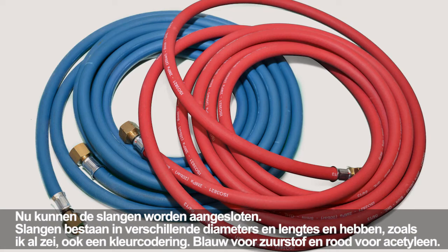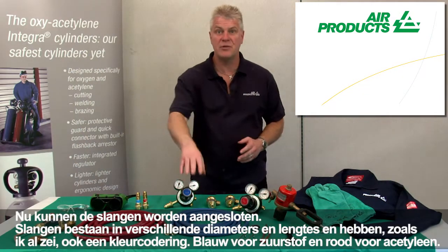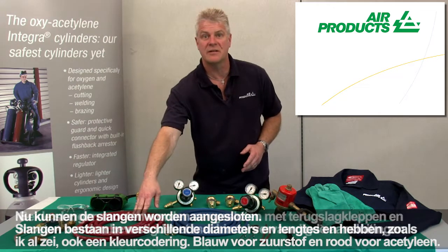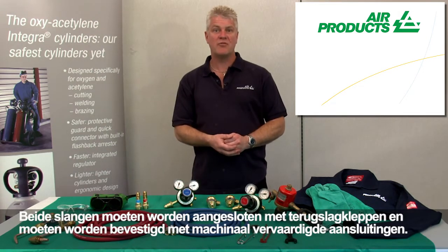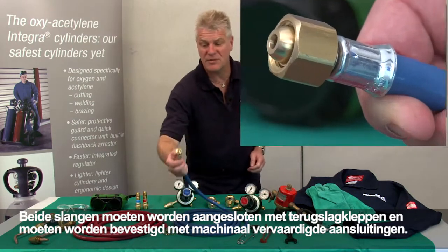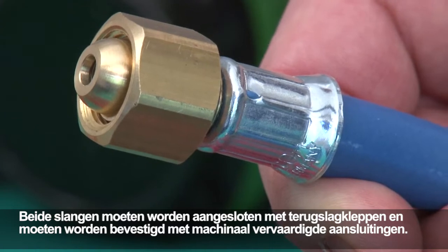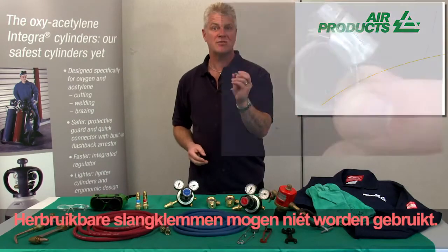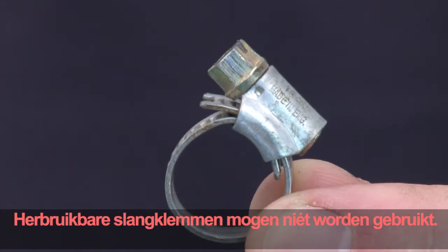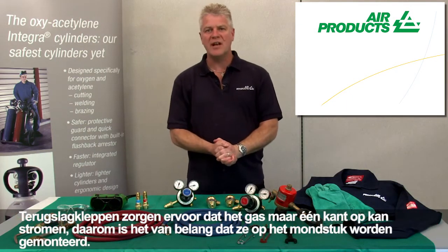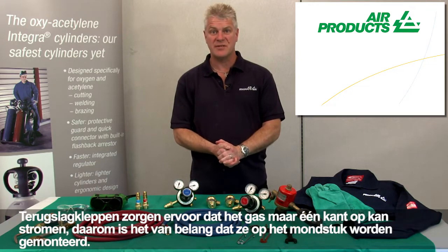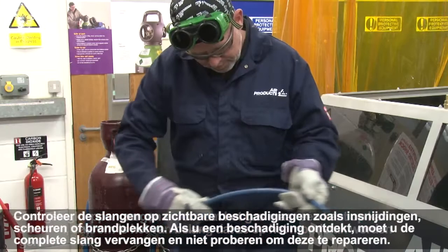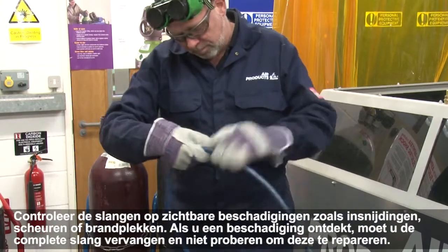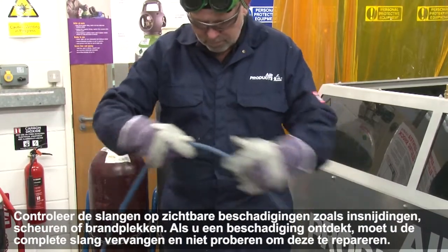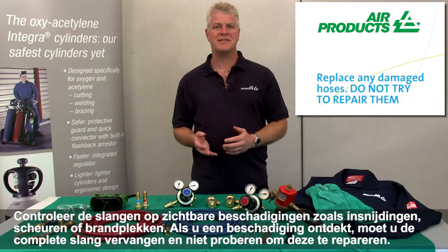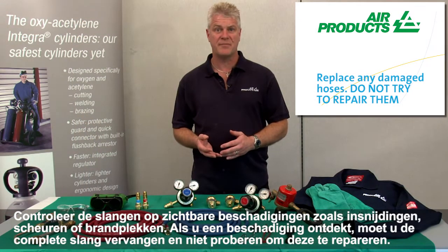Hoses come in various bore sizes and lengths and are again colour-coded, blue for oxygen, red for acetylene. Both hoses should be fitted with non-return valves and secured by machine-fitted connections. Reusable worm drive clamps should not be used. Non-return valves will only allow the gas flow in one direction, so it's important to fit them to the torch. Inspect the hoses for any visible damage such as cuts, cracks or burns. If you find any damage, you must replace the complete hose and don't try to repair it.